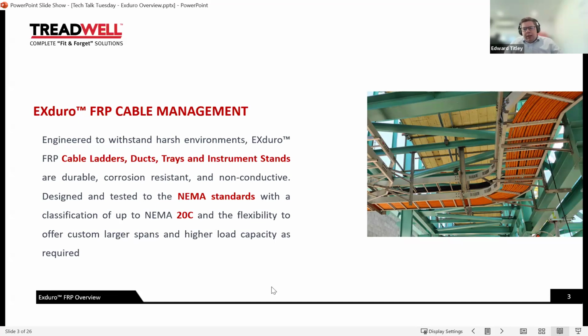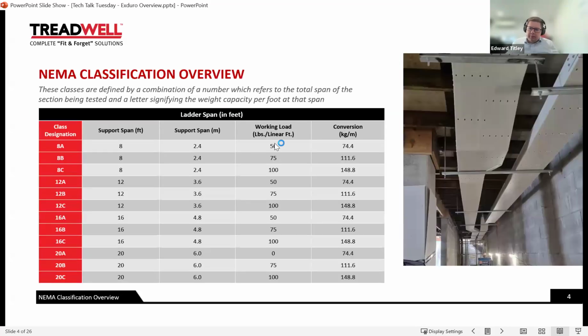We offer a classification which I believe is somewhat unique in FRP cable ladder internationally, up to NEMA 20C classification, so 148 kilos per linear metre and a 6 metre span. Also higher on request, we've worked on some 8.5 metre span cable ladders before, so a lot of flexibility with FRP to keep some slightly non-standard, or shall I say unconventional, applications.